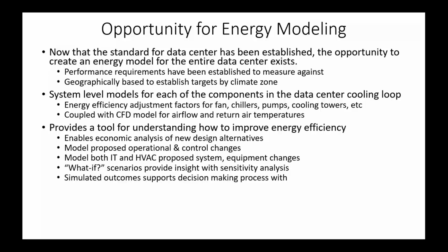It'll even allow you to do things like change the location of the data center. What if we were to take a given data center and put it in Oregon versus Florida? Should we use an evaporative system versus an air-cooled chiller? These kinds of decisions can now be calculated, can now be modeled. Things like changes in control strategies can be done. What-if scenarios? What if I lose something? What if a chiller goes down? What if the second data center or the room that I'm putting on this plant is not going to come up for a period of time? This helps you in the decision-making process because it allows you to understand the implications of those things.